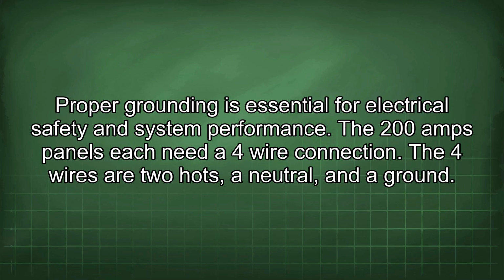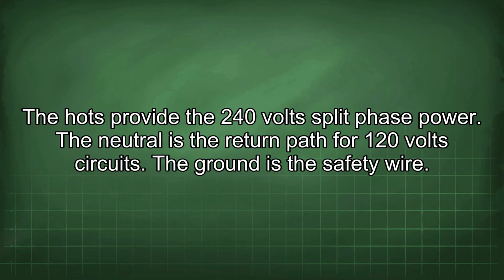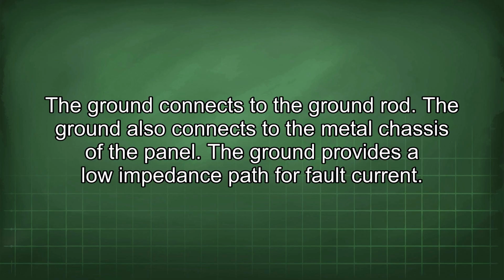The 200 amp panels each need a 4-wire connection. The 4 wires are 2 hots, a neutral, and a ground. The hots provide the 240-volt split-phase power. The neutral is the return path for 120-volt circuits. The ground is the safety wire. The ground connects to the ground rod. The ground also connects to the metal chassis of the panel. The ground provides a low impedance path for fault current.